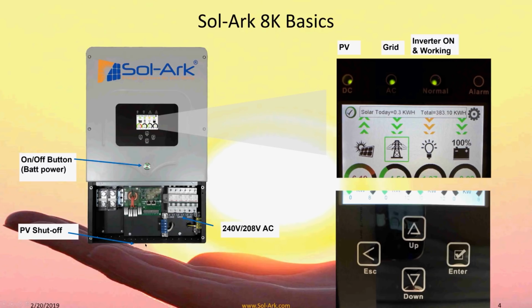There's a PV shutoff down below the system that turns on and off the solar panel inputs. There's also a grid input that can handle 240 or 208. And there's a front on-off button, which basically turns on and off some of the battery power. If I have any one of these 3 power sources, or multiples of them, the computers will stay on and the screen can still be used. This is important for debugging if you have a wiring mistake or something not done correctly. So if I want to fully power down the system, I have to turn off all 3 sources.